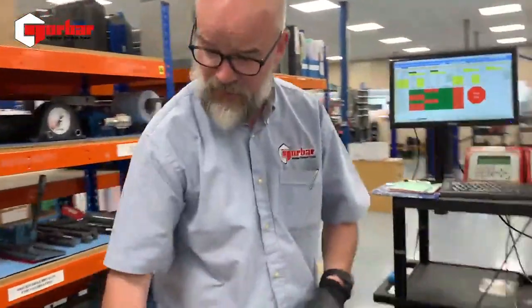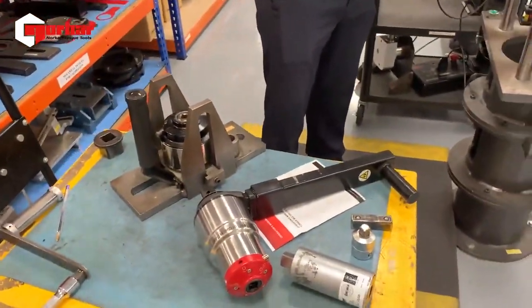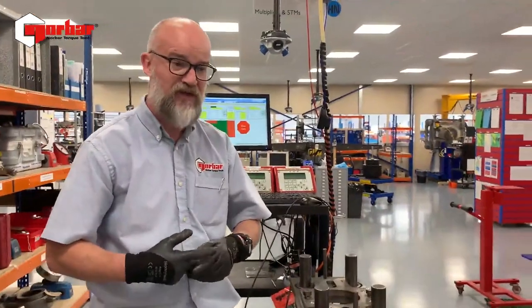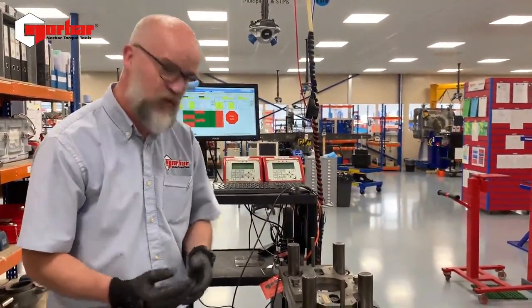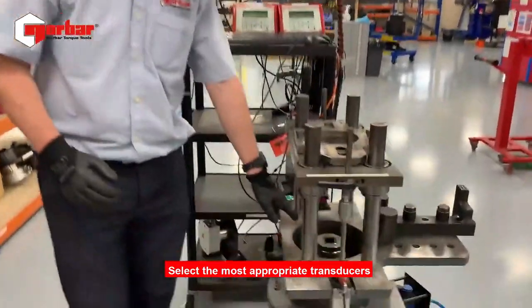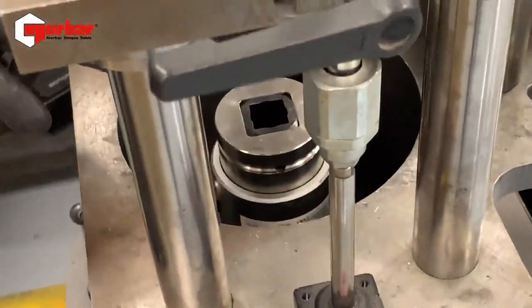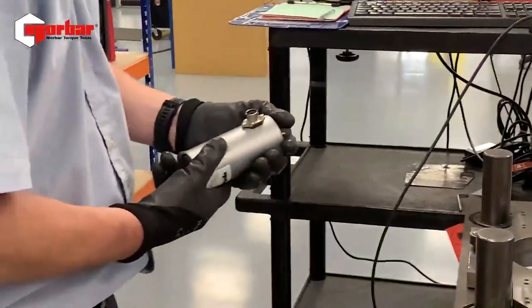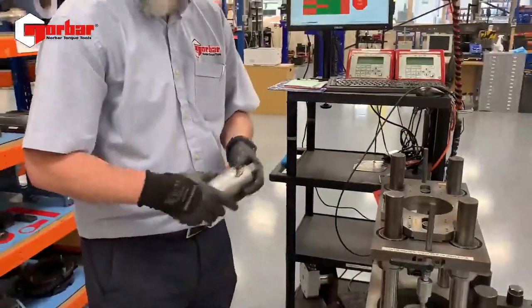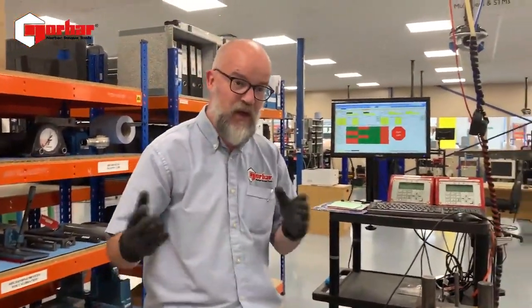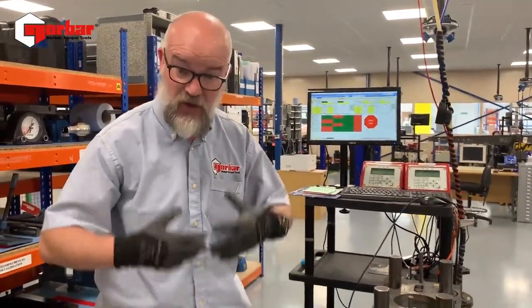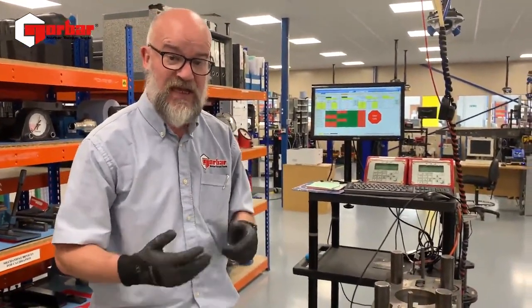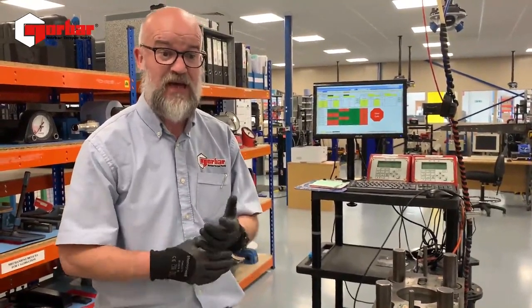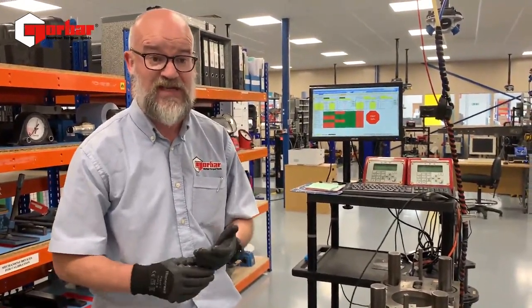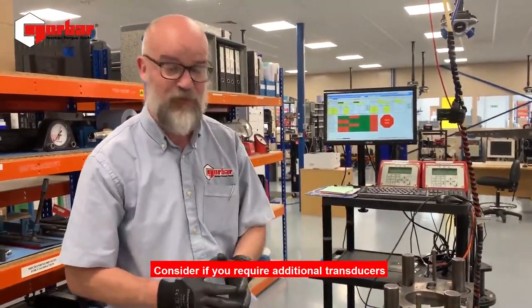Okay, so I said that we were working with a 4000 Newton meter HandTorque. Norbar's laboratory is very fortunate. As we manufacture transducers, we've got many to choose from, and what we want to do is select the best fit. So I've got a 5000 Newton meter transducer measuring the output torque, and I'm going to be using a 250 Newton meter transducer measuring the input torque. So effectively, I've selected quite easily from our large stock of transducers in our laboratory the appropriate transducers. Many end users would have a vast range, and in certain instances you may need to look at investing in a missing transducer to fill maybe a gap within your range.